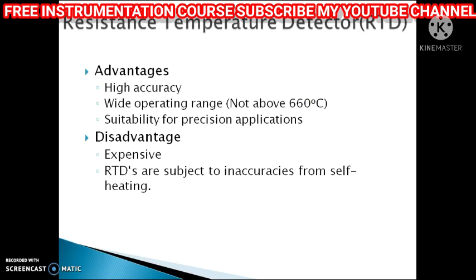The last part of this lesson covers the advantages and disadvantages of RTD. Advantages include: first, high accuracy — the platinum RTD has a linear relationship and gives accurate results depending on the measurement circuitry. Second, wide operating range — the standard RTD operates from minus 200 degrees to 660 degrees Celsius, with 660 degrees achievable using platinum RTD. Third, suitability for precision applications — due to high immunity to electrical interference and long-term stability, RTDs give very precise readings.